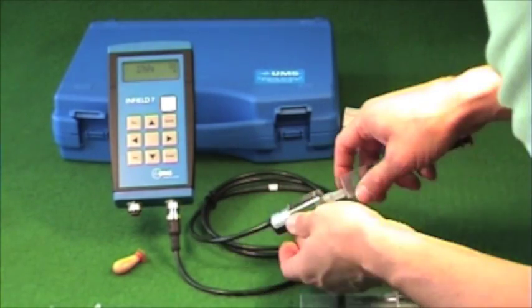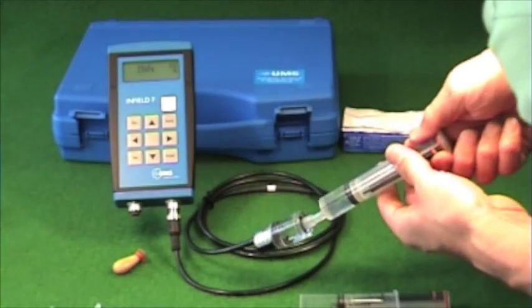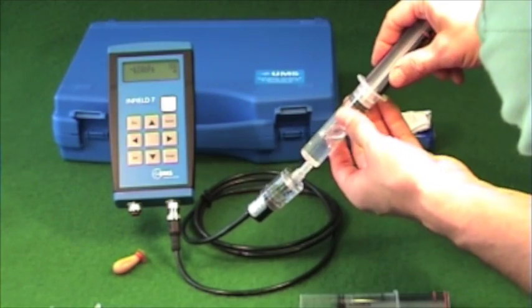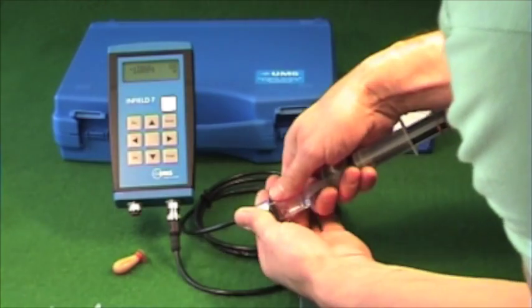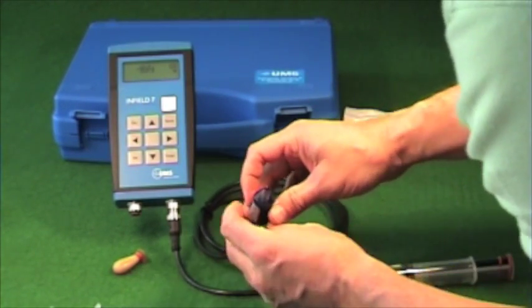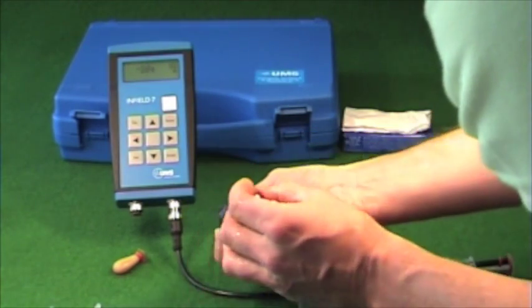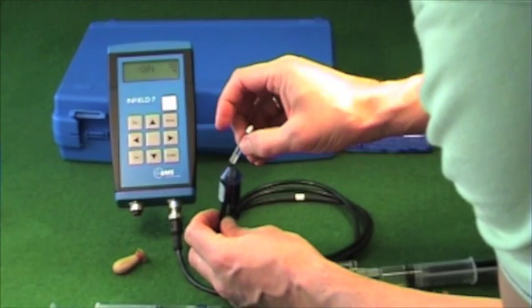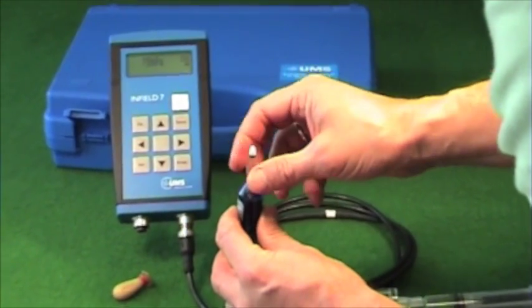Now remove the sensor body. Check if all bubbles are removed. Before you screw both parts together, add one drop of water onto shaft and body so a bulge of water overlaps and be sure no air bubble slips inside. Screw the shaft carefully into the sensor body.